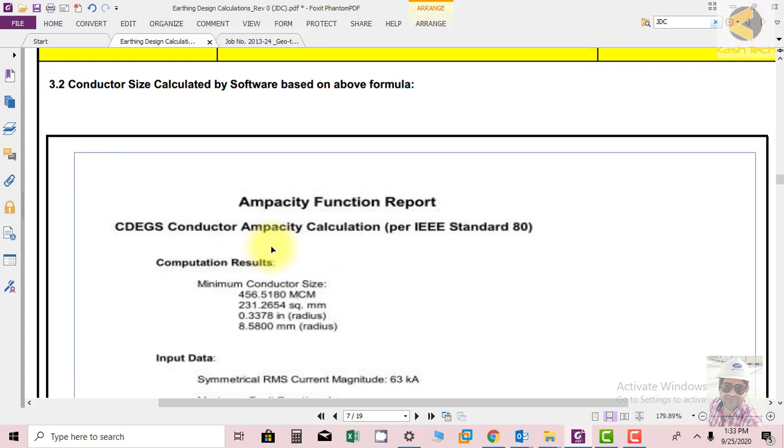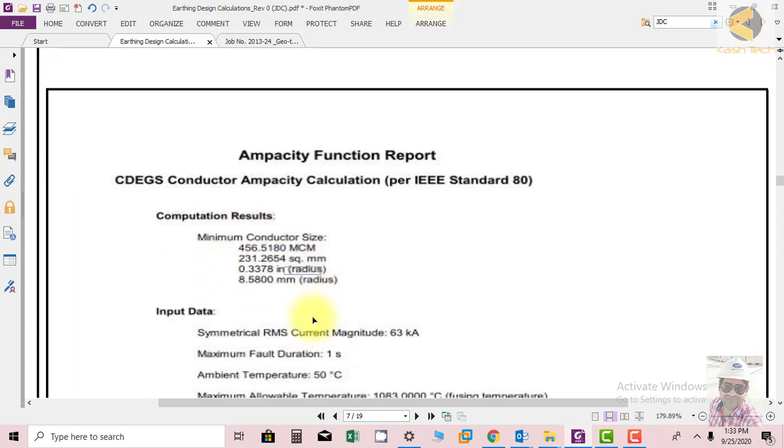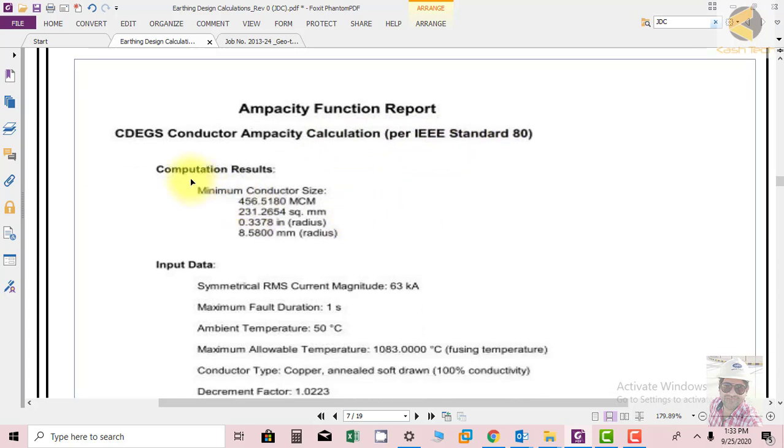We have explained the formula but actually the conductor size, when you put the data, will be calculated automatically. You see the results which are coming from CDEGS directly. These are the CDEGS conductor ampacity calculations and we are following IEEE 80. These are the computation results. Minimum conductor size is 456 MCM, 231 square mm.